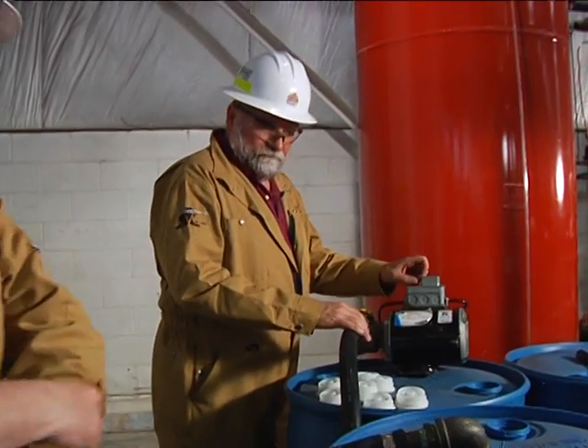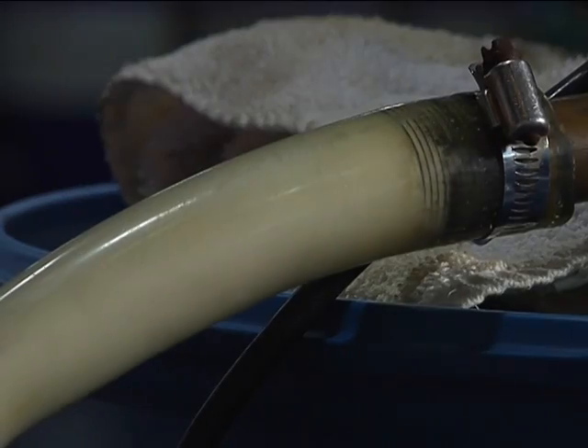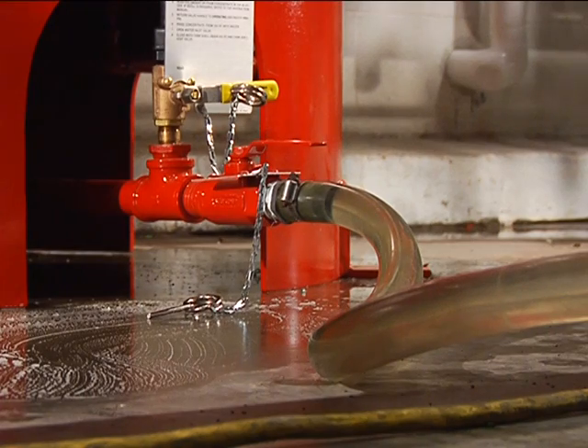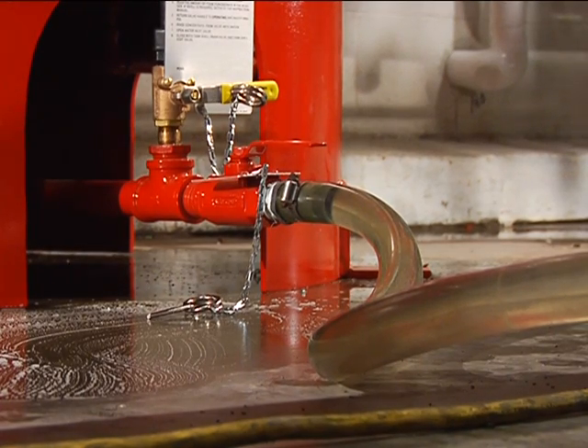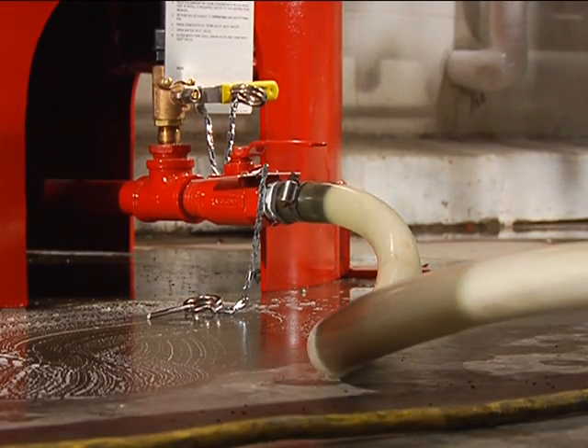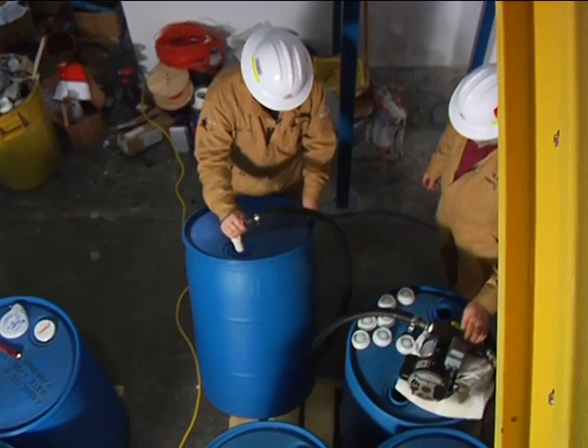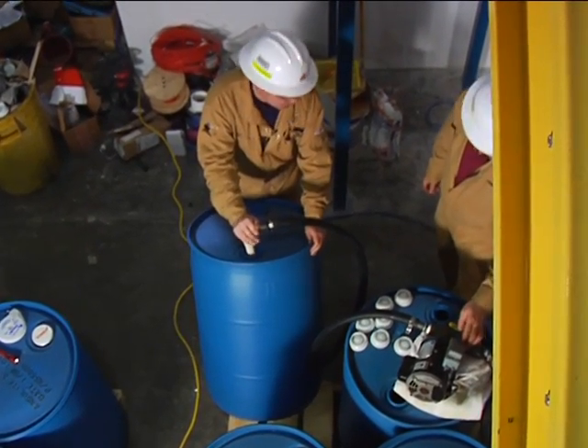Next, start the concentrate pump, open the pump valve, and build up the pump pressure. Slowly open the bladder drain fill valve and start pumping the concentrate into the bladder until the amount of concentrate stamped on the tank nameplate has been pumped into the bladder.